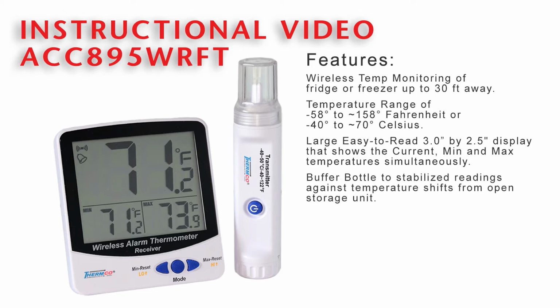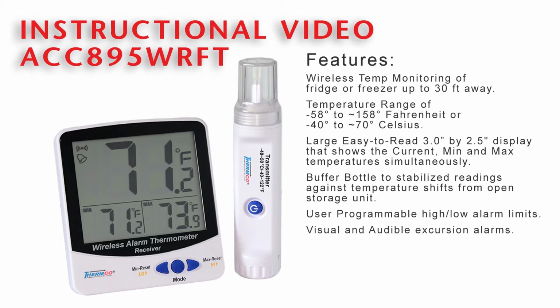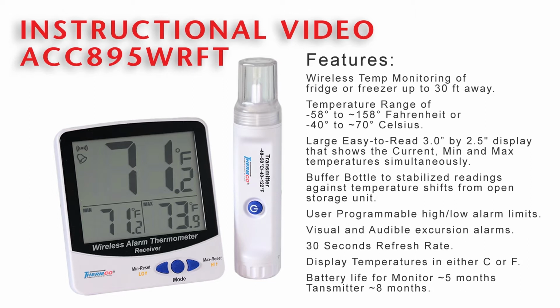The wireless probe has an integrated bottle filled with biosafe medium to buffer readings against temperature shifts caused by opening of storage unit doors. User programmable settings for high and low alarm limits with visual and audible alarms during excursions. The temperature refresh rate for the wireless probe is every 30 seconds, with the choice of displaying temperatures in either Celsius or Fahrenheit. Battery life for the monitor receiver is approximately 5 months and 8 months for the transmitter using AAA batteries.